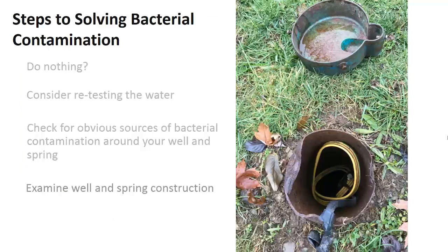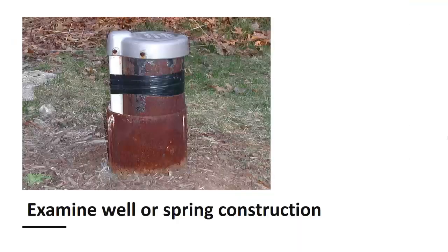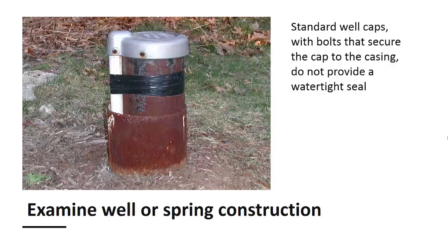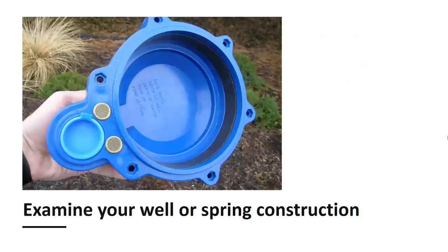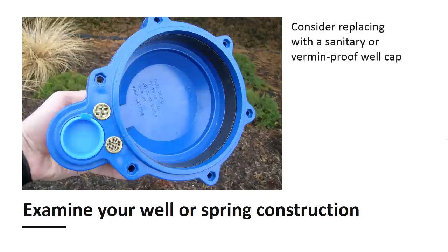A fourth step for solving bacteria problems is to examine your well or spring construction. Here, a bent well casing allows for openings under the well cap that provide easy access for insects and small mammals. Make sure your well casing extends above the ground surface and is intact to prevent contamination. If needed, new pieces of casing can be welded onto the existing casing to make necessary repairs. Take a close look at your well cap. Make sure it is tightly secured to the casing and is sealed to prevent insects and surface water from entering the well. Standard well caps with bolts do not provide a watertight seal and can be a common cause of bacteria problems. Consider replacing it with a sanitary or vermin-proof well cap, which has a rubber seal inside the cap preventing insects and surface water from entering the well.